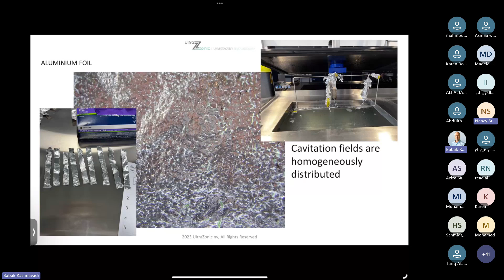Can you click again on that? This is from another brand, also the validation of their ultrasonic device, and you see in these stripes here and there some little bubbles, but they were putting these aluminum foils, I think, for more than 3 minutes in the ultrasonic device, and this is the result. So I advise you, please get an aluminum foil, put it around the frame, and just time it. When you need more than 30 seconds to get some bubbles, it means your ultrasonic device is way too weak to clean your instruments. So this is just a little job to find out yourself if you have a good ultrasonic cleaner or not. Next, please.